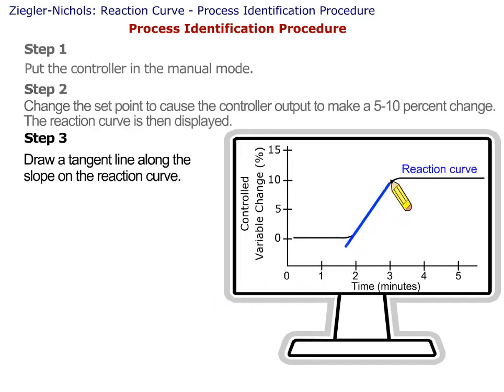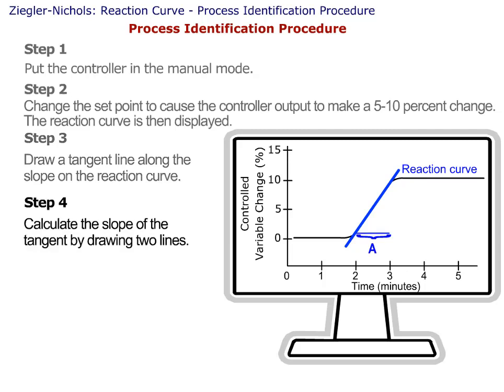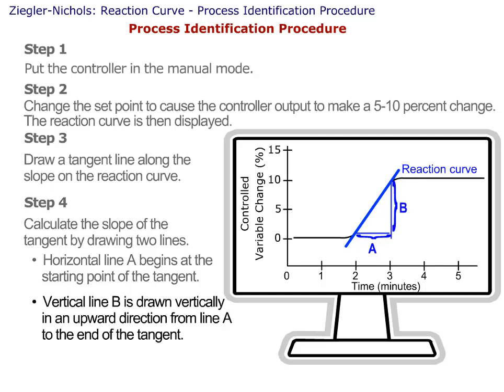Step 3: Draw a tangent line along the slope on the reaction curve. And Step 4: Calculate the slope of the tangent by drawing two lines. Horizontal line A begins at the starting point of the tangent. Vertical line B is drawn vertically in an upward direction from line A to the end of the tangent.